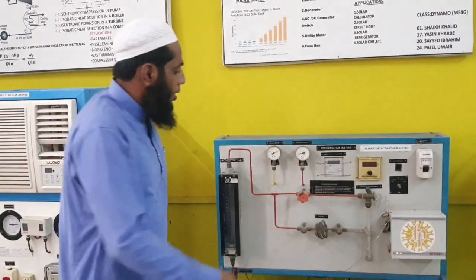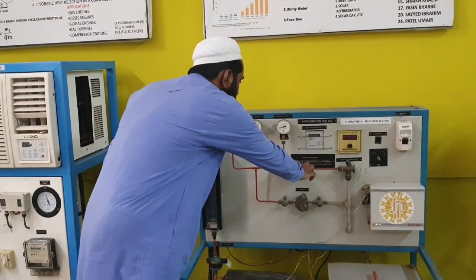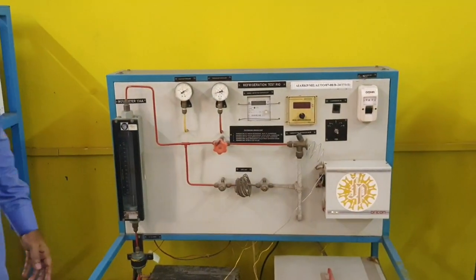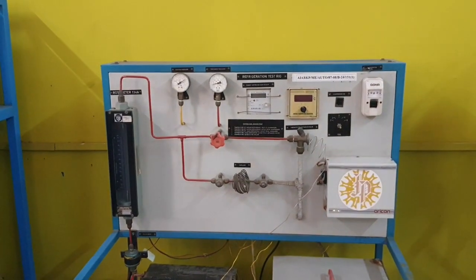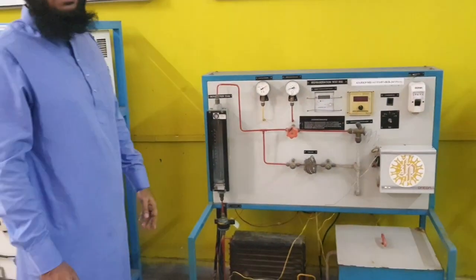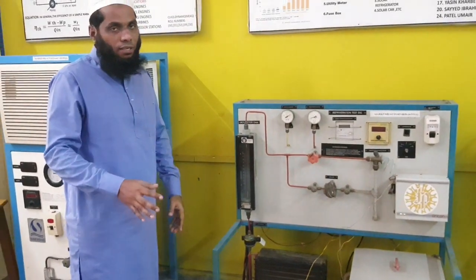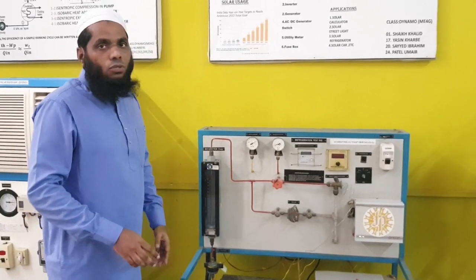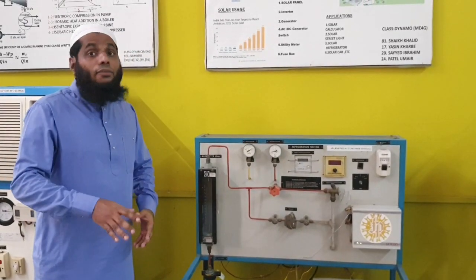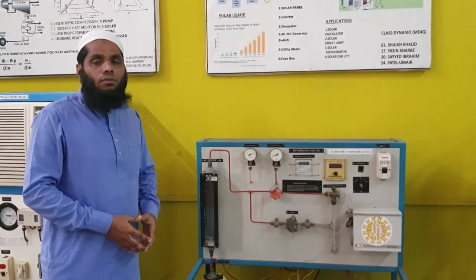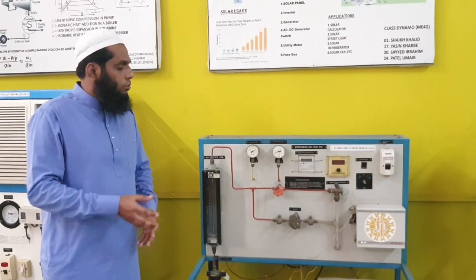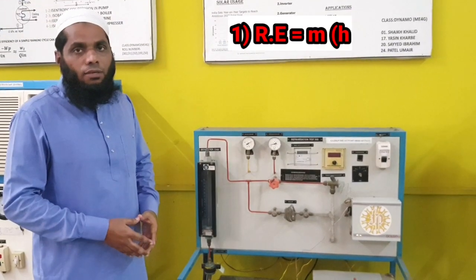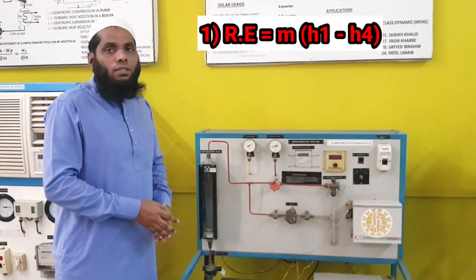After that, we determine the evaporator zone values. We measure the temperature of the liquid refrigerant before the evaporator, which is coming from the expansion device. For that, we have enthalpy value H3, and since H3 and H4 are the same, H4 is also determined. The refrigerating effect is the cooling effect produced inside the evaporator, which is M — mass of refrigerant — multiplied by H1 minus H4.